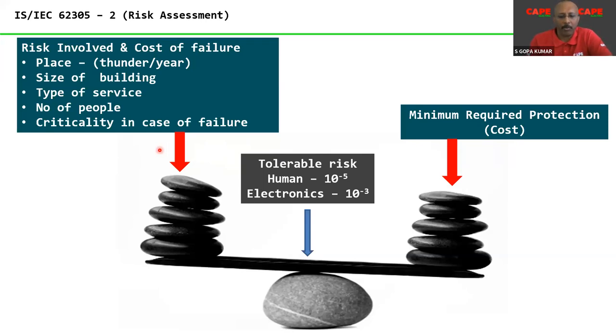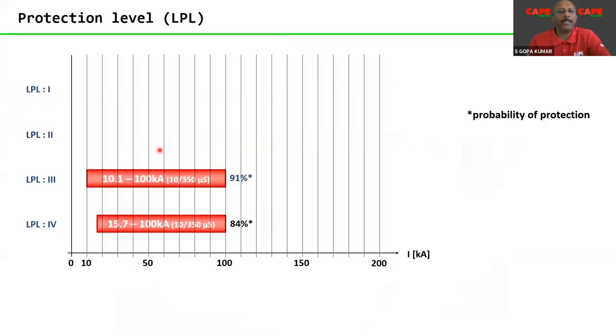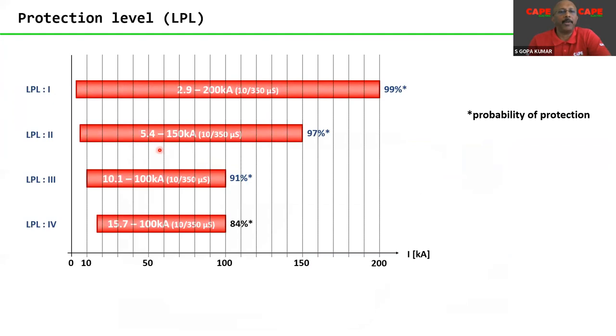Risk assessment is more made for a typical structure or a typical building, just to find out whether lightning protection is necessary or not. If necessary, lightning protection is classified into four levels. Level 1 to 4, depending upon the current, for example, level 1, 2.9 to 200 kiloampere. Level 4, 15.7 to 100 kiloampere.